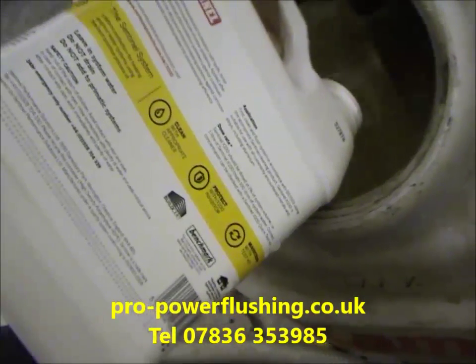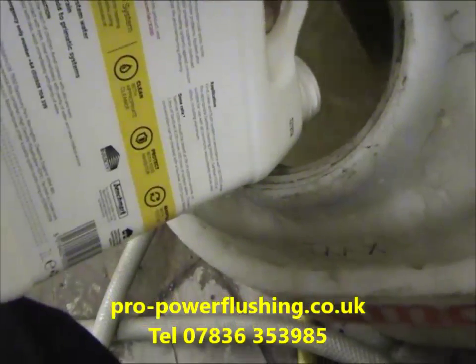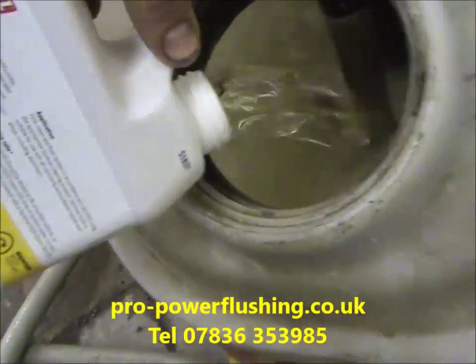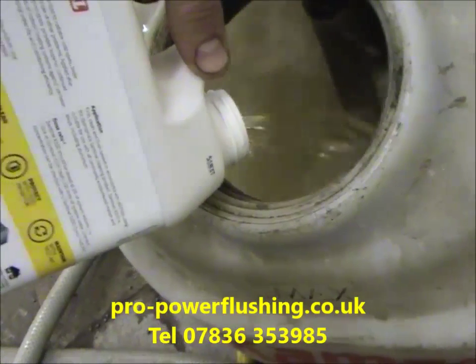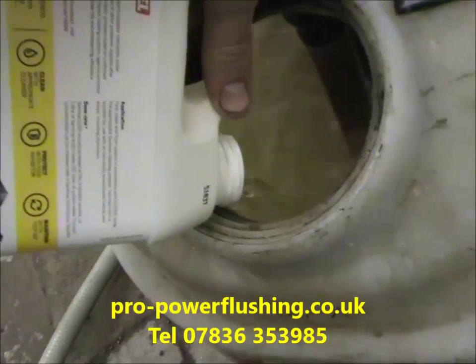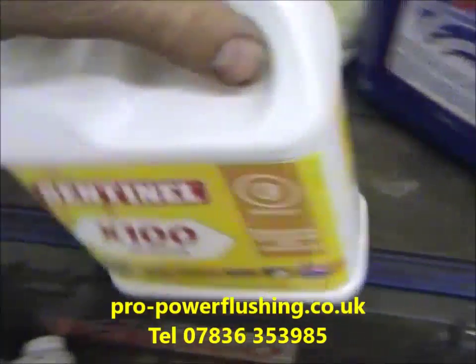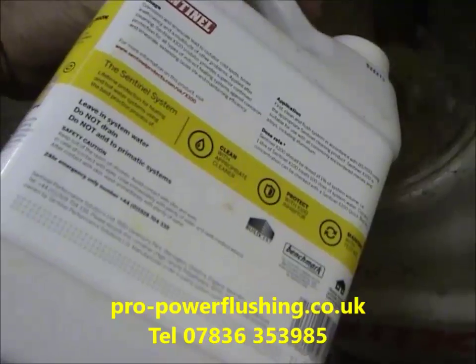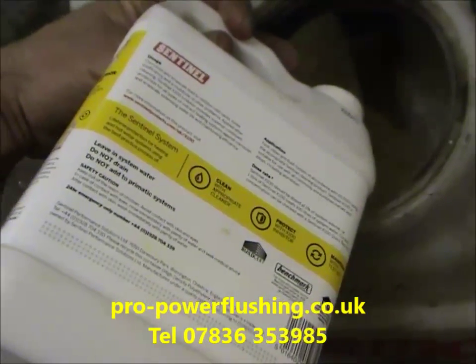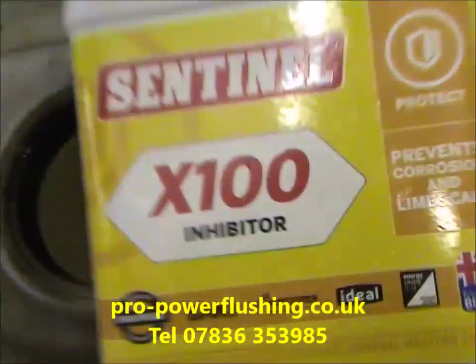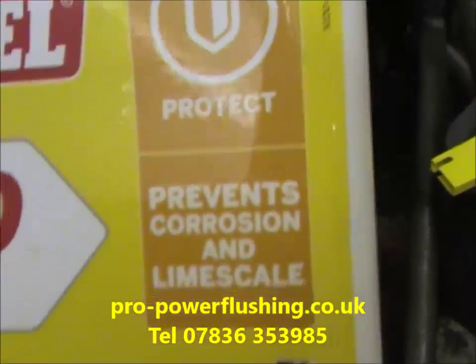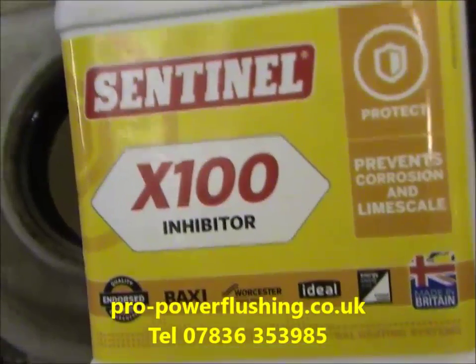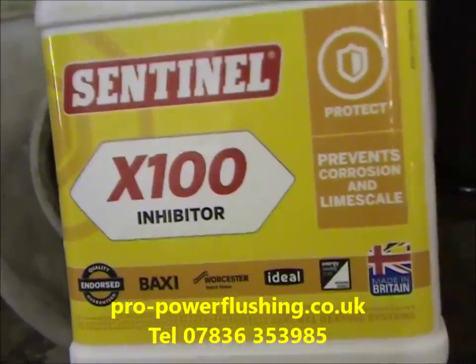Fairly big system this, about 30 radiators, so that's why we're adding 3 litres of Sentinel X100. Circulate around for 10 minutes, just make sure it's coming back to the machine, get it into the whole system, and that's just to prevent further rust, corrosion and limescale from affecting the system. Okay, job's going alright, we'll get back to you later.